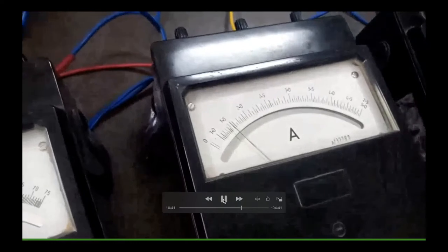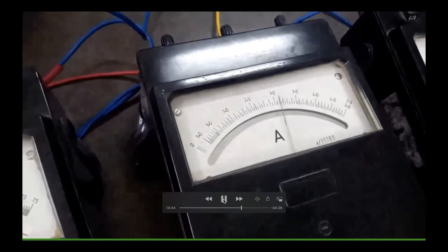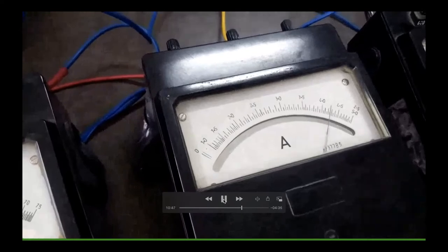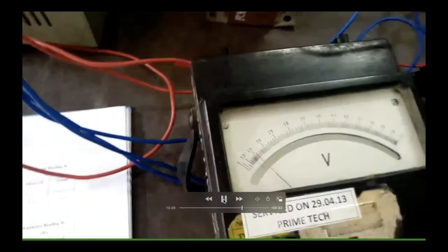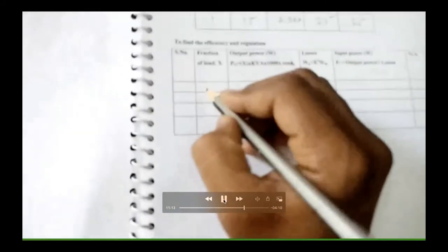Turn on the supply and now keep the rated current. For short circuit, you have to keep the rated current 4.5. So only one value, you have to keep as 4.5. So you can see, 4.5 corresponding voltage 15, and the corresponding wattmeter reading is noted. Multiplication factor is 1. 15, 25, 25. That's all. So only one reading. So bring back to the positions and turn off. And then we can go to the calculations.